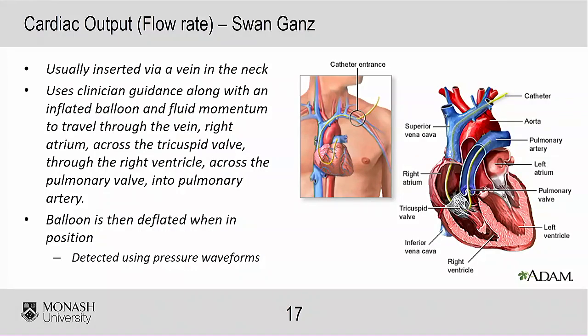And the way you detect if it's in position is, as I mentioned, it has a pressure sensor on the tip of the catheter. So as it comes through, first of all, we know what right atrial pressure typically looks like. It's a very small oscillation in pressure, so we know we're in the right atrium. We then go through the right ventricle, and typically right ventricular pressure goes between about 2 millimeters of mercury and 25 millimeters of mercury in a regular peak and trough. Then, when we see it go through the pulmonary artery, it goes between about 25 and 10 to 15. So we see a change in pressure as it's going through. We know exactly where it is. So it's a very neat device.